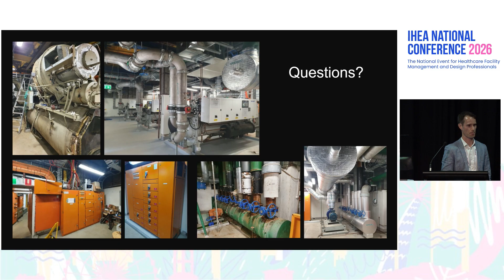The mechanical switchboards were probably the biggest, or caused the biggest amount of grief, so I think trying to split those up a little more. The requirement was for N+2 in the plant, but we only had 2 switchboards, and that's the way it was originally. Only having 2 switchboards meant we couldn't technically achieve the N+2 requirement. So for next time, if we had 3 or 4 boards and the space, we could have broken it up a little more to provide that level of redundancy.